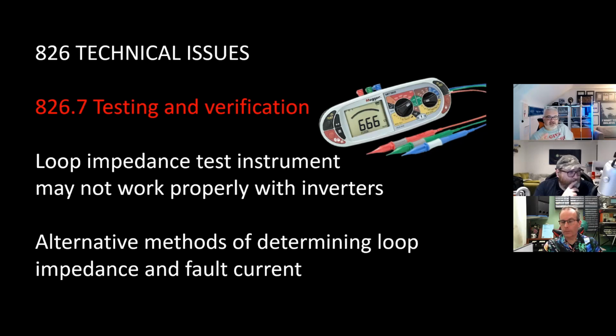This, I would never calculate it, but I'm well aware that some manufacturers say, please don't put 23 amp high current tests through my equipment. Yeah, and there must be a way you can just temporarily bypass. Well, the MFT 1741 Plus apparently has got this confidence meter, and they have said that it will work on inverters. It will filter it out and give you a reasonably accurate reading. There are videos online of that.